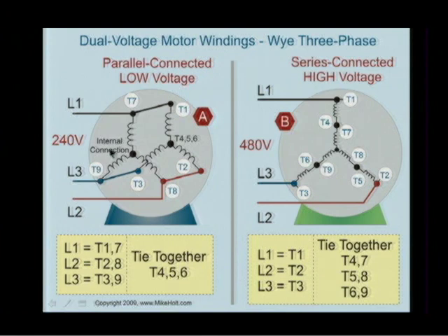That means I'm connecting these windings in parallel to each other, aren't I? So these 3 windings right here are going to get connected to 230. These 3 right here are going to end up getting connected to 230 as well. That's for the lower voltage. If I go to 480, that means that this voltage here is operating at kind of like 120, 120, 120, 120, 120, 120. And then when I go to 460, I'm going to connect these 2 windings in series to each other at 460.